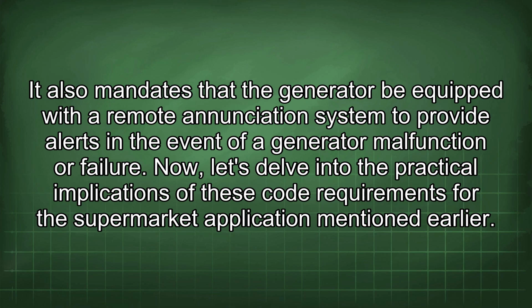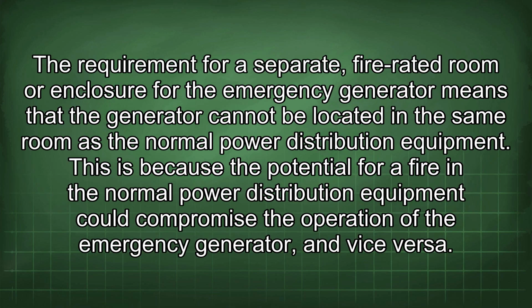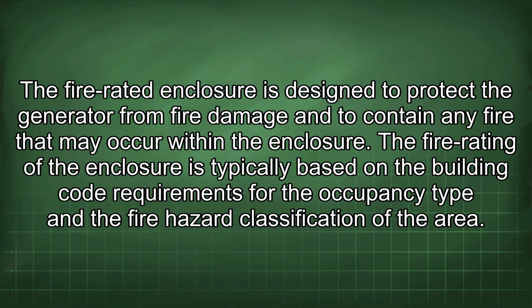Now let's delve into the practical implications of these code requirements for the supermarket application mentioned earlier. The requirement for a separate, fire-rated room or enclosure for the emergency generator means that the generator cannot be located in the same room as the normal power distribution equipment. This is because the potential for a fire in the normal power distribution equipment could compromise the operation of the emergency generator, and vice versa. The fire-rated enclosure is designed to protect the generator from fire damage and to contain any fire that may occur within the enclosure. The fire rating of the enclosure is typically based on the building code requirements for the occupancy type and the fire hazard classification of the area.